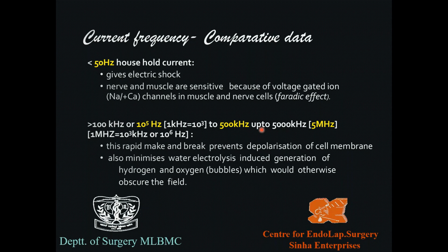So there's no depolarization. If there's no depolarization, there'll be no nerve stimulation, there'll be no muscle stimulation. And in addition to that, it also minimizes the water electrolysis, the generation of hydrogen and oxygen bubbles, which would otherwise obscure the field. Now, that will no longer obscure your field. And number two, it will no longer electrocute you, or accidentally even the patient. There will be absolutely no shock to the patient because of the very, very high frequency. So this comparative data helps you. From 50 hertz, we are talking about 10 to the power 5, right? That is what we're talking about, or even up to 10 to the power 6 hertz.